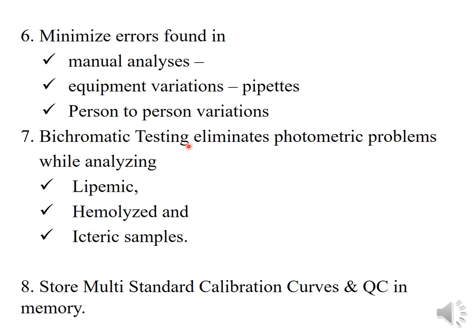There is a very good facility in auto-analyzers called bichromatic testing, through which two wavelengths can be used to measure a single analyte. This eliminates photometric problems while analyzing samples that are lipemic, hemolyzed, and icteric.